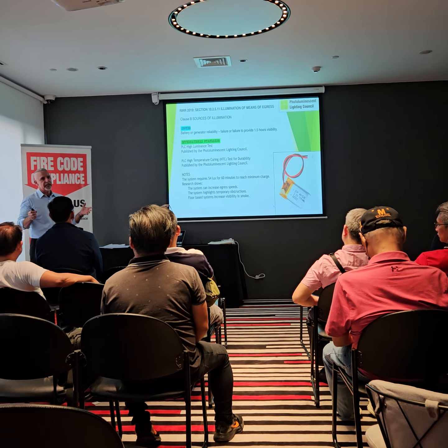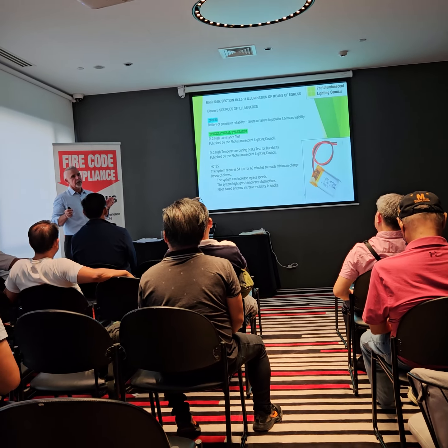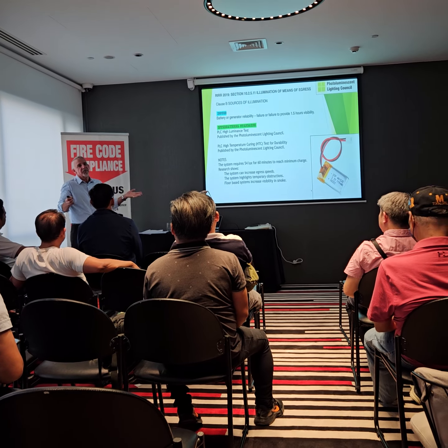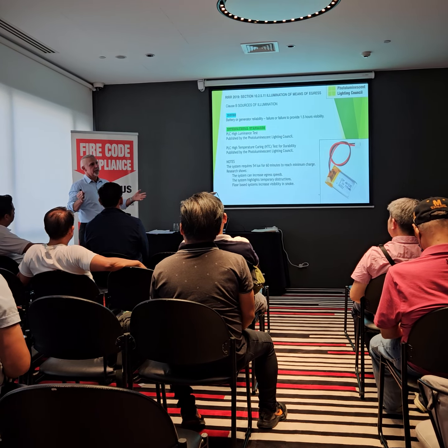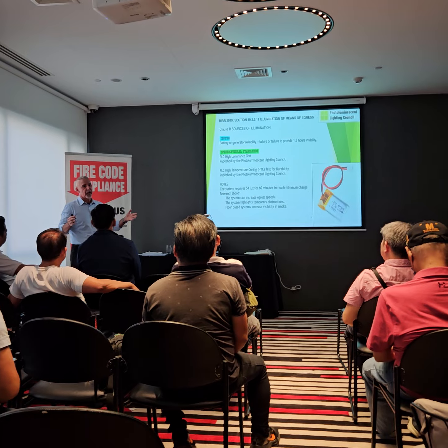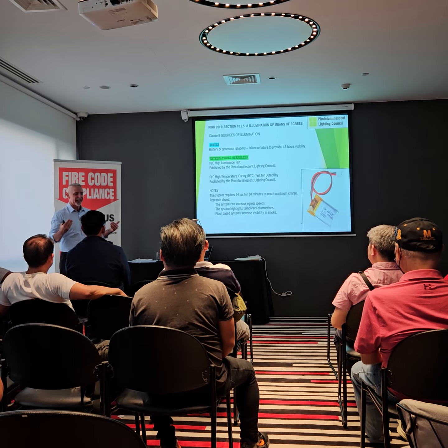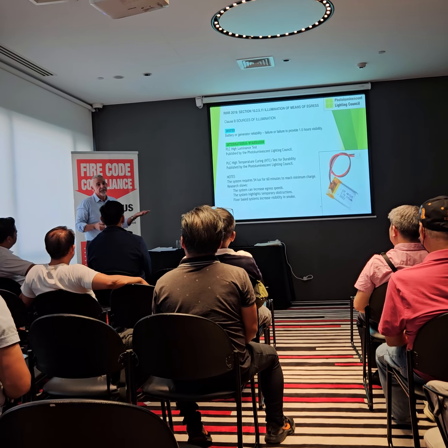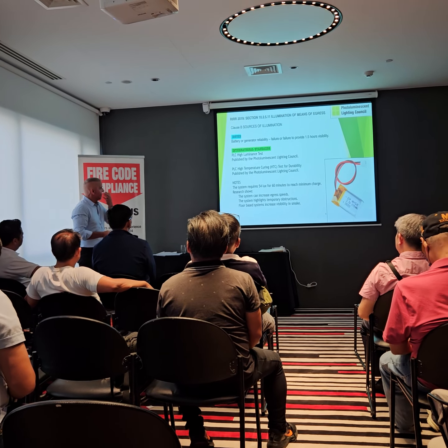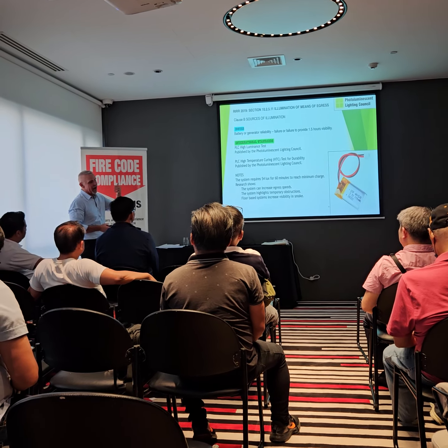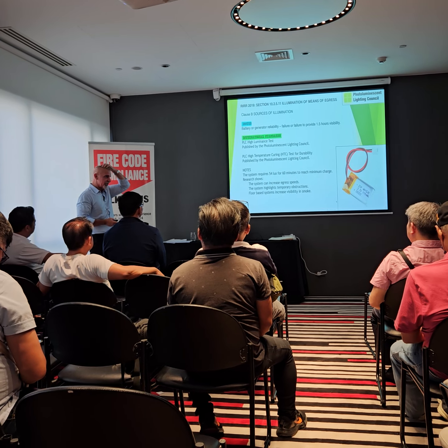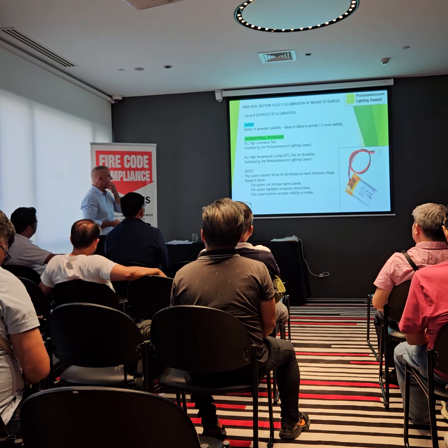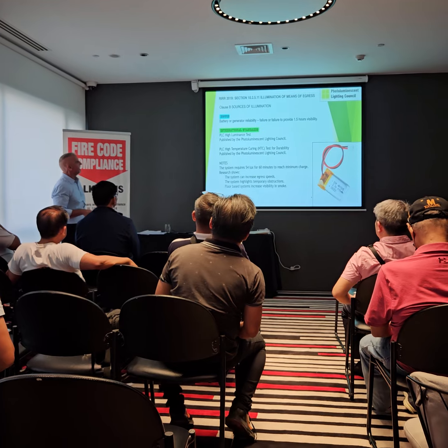Basically 80% of the generators in San Francisco failed. They didn't come on because the whack and the shock of the earthquake just gave something a nudge, whether it be wiring or something, and they just didn't fire. So that's, I think, part of the reason that there's such a push for these systems in the US now. They've seen things go wrong.